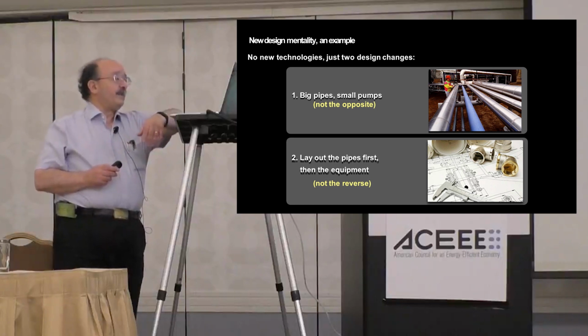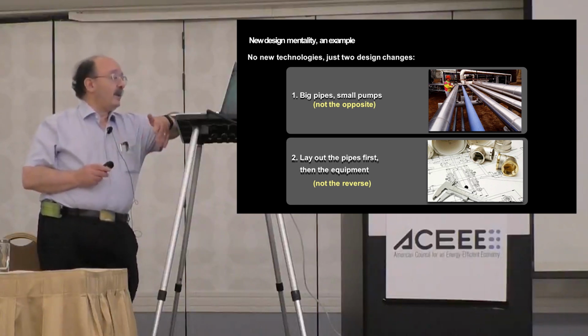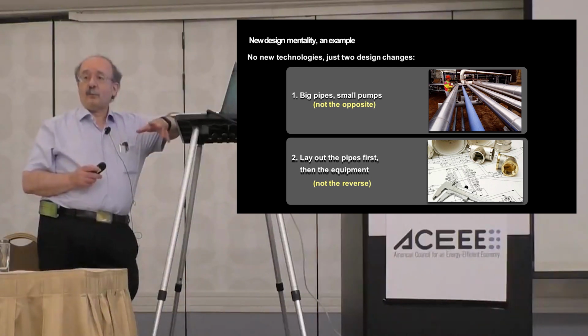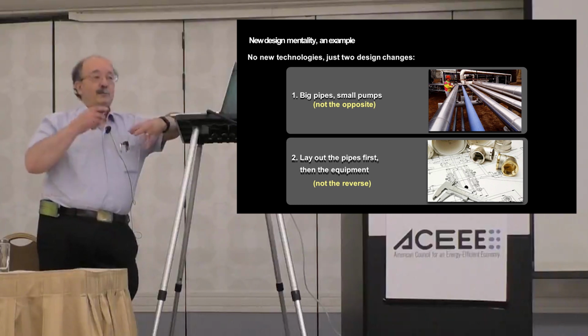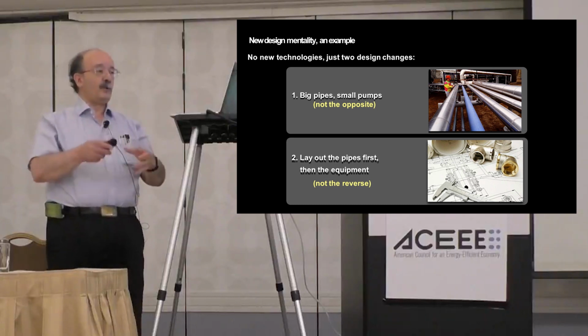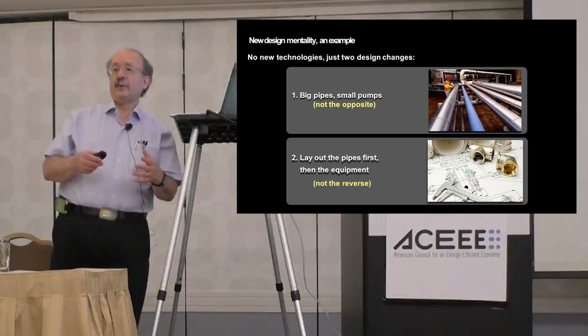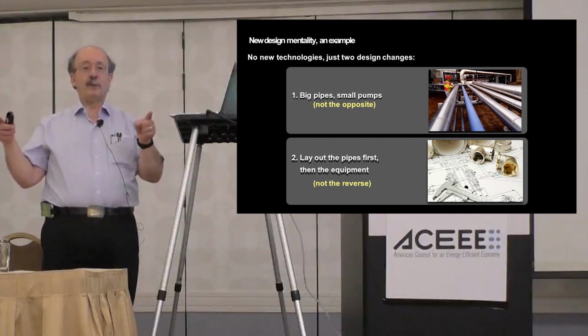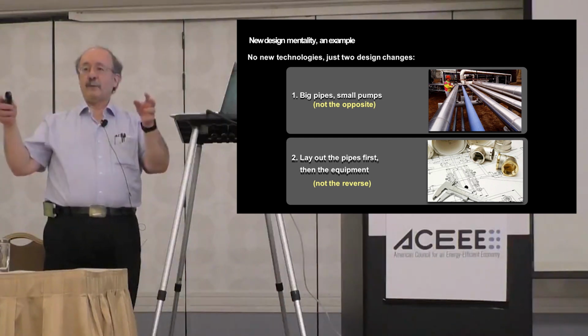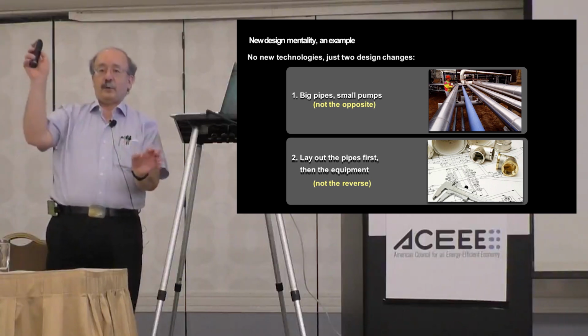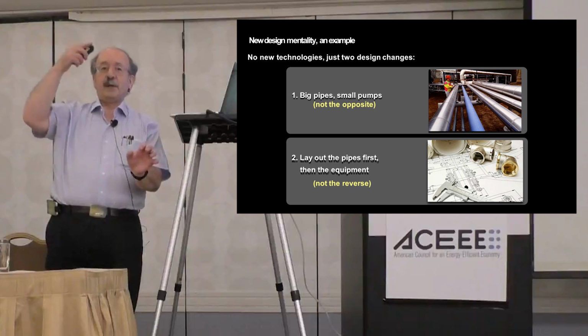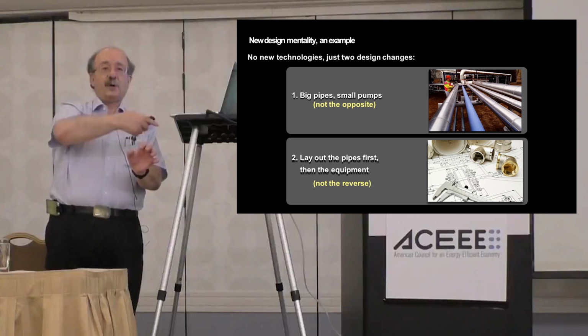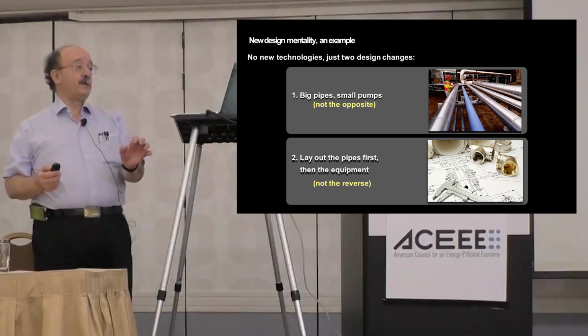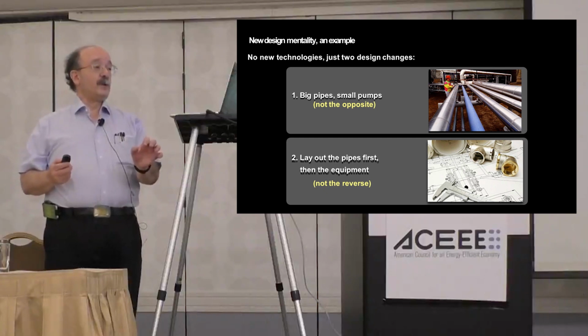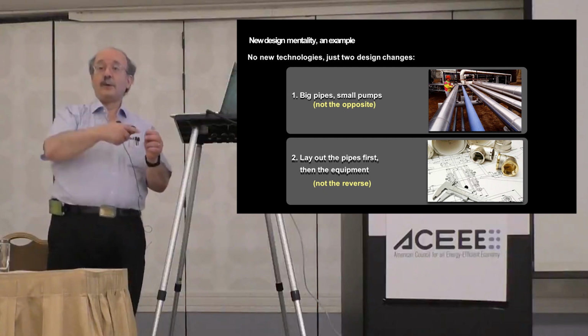That's laying out the pipes first, then the equipment. That's the opposite of normal practice, where you put the tanks, boilers, whatever, in some traditional, arbitrary, convenient place, and then call in the pipe fitters and say, please connect point A to point B. But by then, A and B are rather far apart. Other stuff got in the middle. They're the wrong height, they face the wrong direction. By the time the pipe snakes across the space, dressed neatly at right angles like they teach us in trade school, the friction is 3 to 6 times what it would have been with a straight shot.